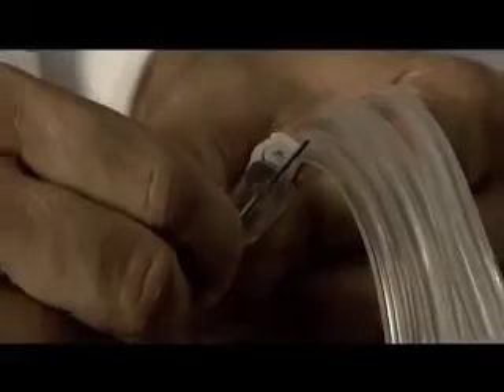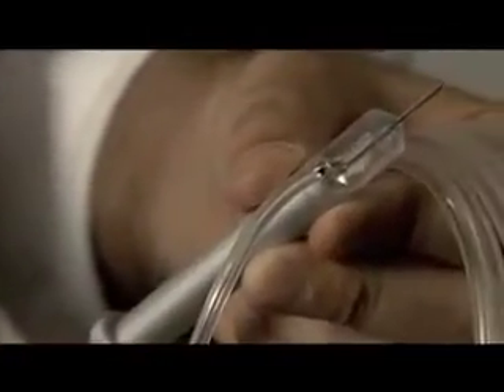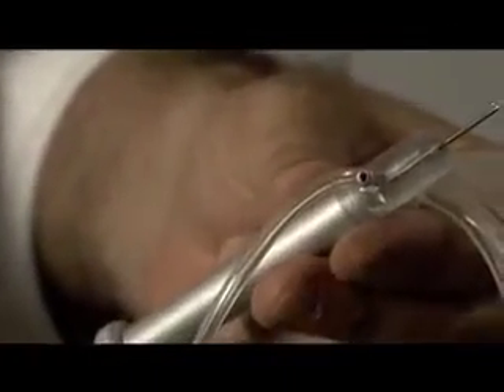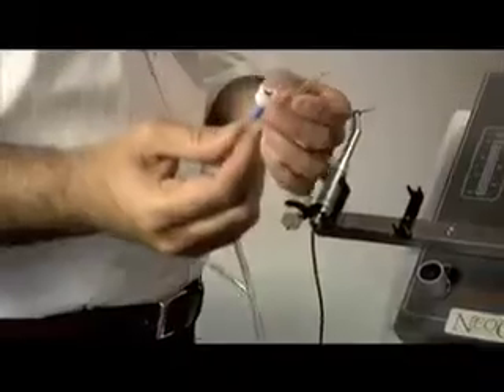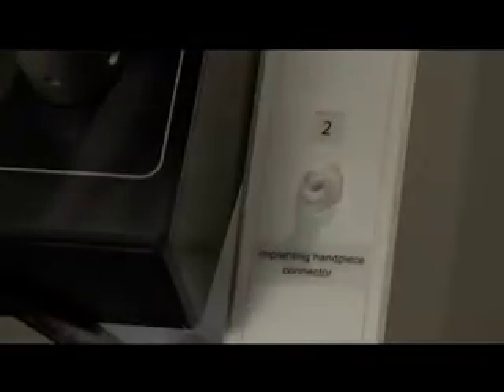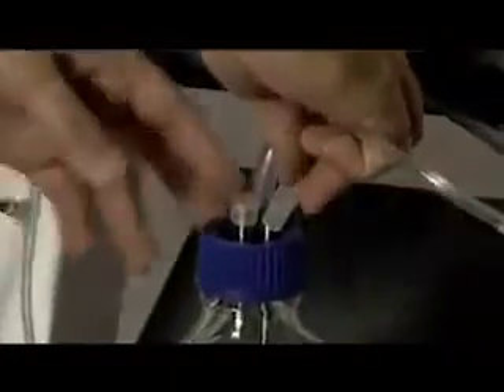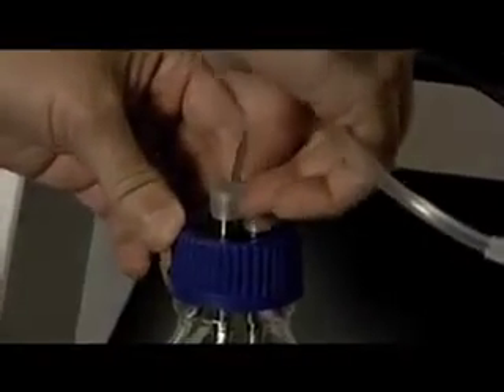The smaller end of the tubing connects to the port on the side of the implanter handpiece head by sliding it over the port. Replace the implanter handpiece onto the cradle. Now connect the other ends of the tubing set. The other blue-banded tube is connected to port 2 on the right side front of the unit, marked Implanting Handpiece Connector, by pushing in and turning to the right to lock. The other end of the tube set is connected to the top of the fluid collection flask.